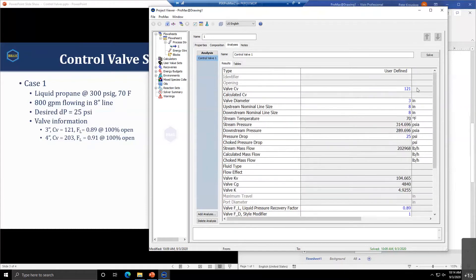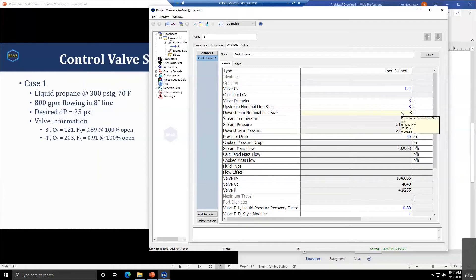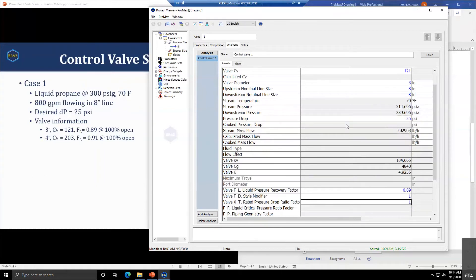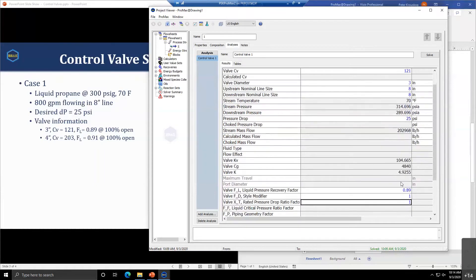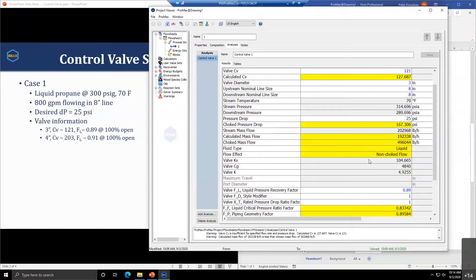Those are the basic inputs needed to size the valve. We need to provide an initial estimate of what we think the CV will be, information about the valve and pipe sizes, and the appropriate values for FL, FD, and XT. Once that information is in, click solve.